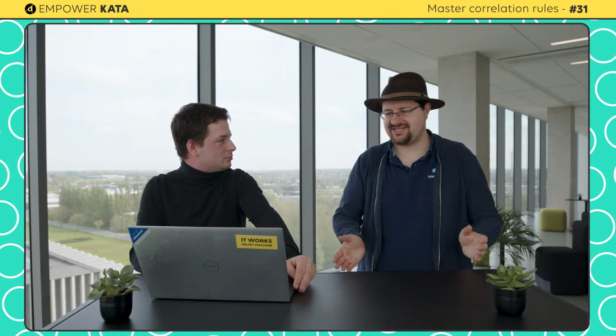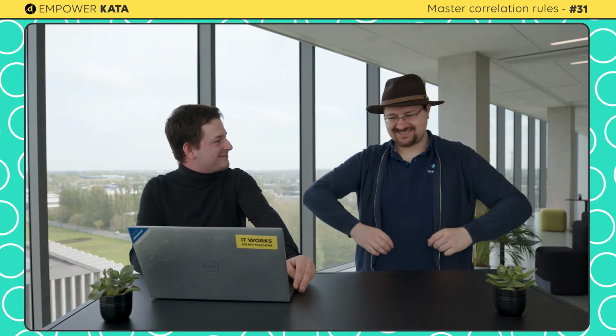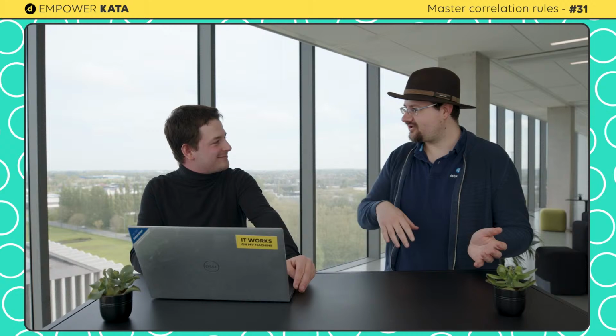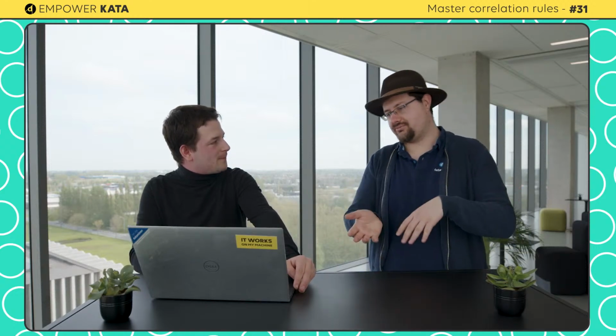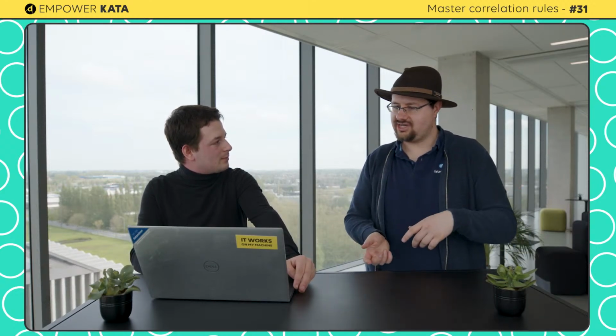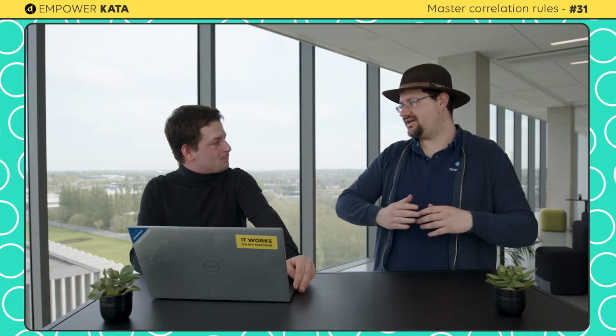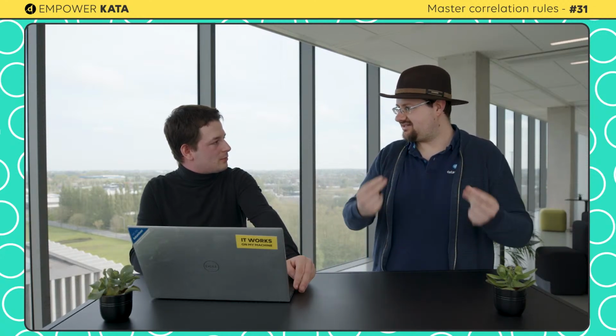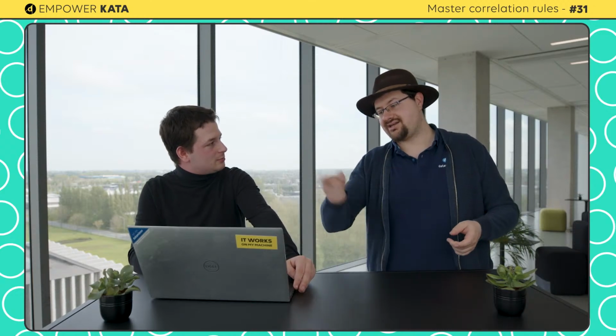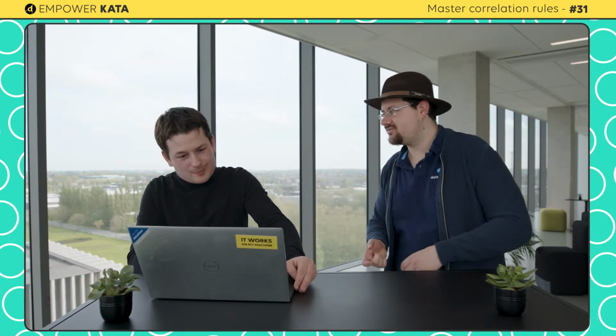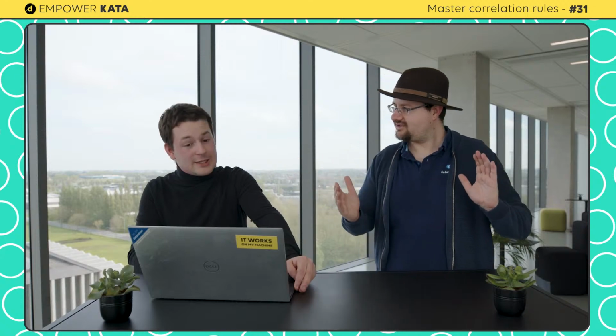If you've got a view and there's like 100 elements in there, and you don't really consider the impact of that, because imagine it's a, what do you call it again? I keep calling it a flapping alarm, but it's not a flapping alarm. It's something else. It's when it goes up and down again, like critical and then normal, critical, normal. So something like that could, if you're not careful, generate an event every time or generate a correlation every time. Potentially yes. But not in the way we're going to do it. No. Because the way we're doing it, we have a time window, right? Yes. Look.